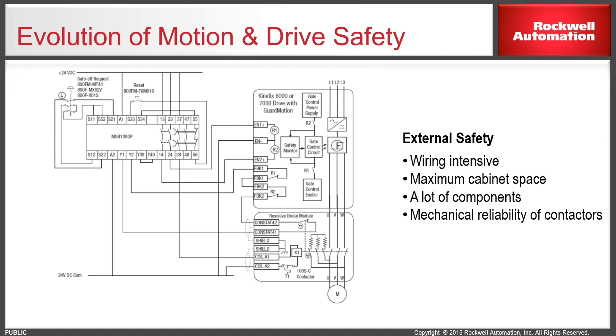Hi, I'm Jeff Hampton. I'm the power and control area manager here in the Detroit sales office for Rockwell Automation. Today, we're going to update you on some advanced safety functions that were released in the latest version of Rockwell's drive and motion product family. There's been a lot of improvements in the way safety is implemented in drives and motion today. If you take a look at this slide, this is an older architecture where we use safety relays, hardwired inputs, contactors between the drive and the motor, or potentially contactors ahead of the drive. While it did provide a safe system, there were some negative impacts that could occur if a contactor was opened at the wrong time or cycled on and off very quickly. You can damage drives and drive motors.